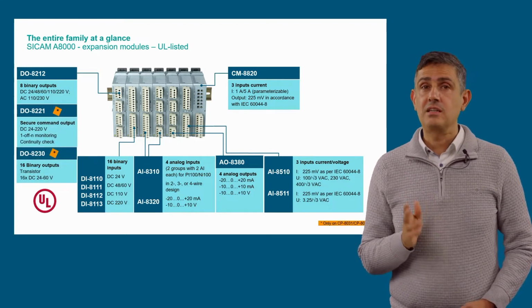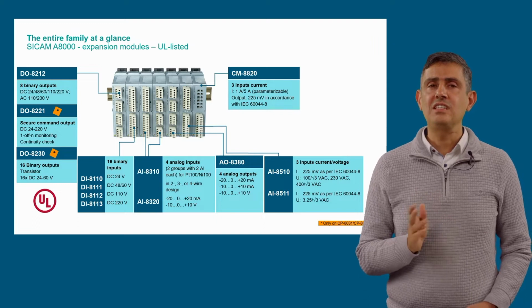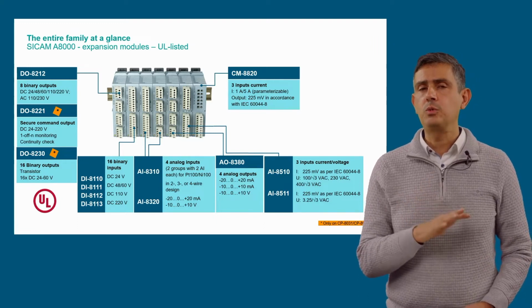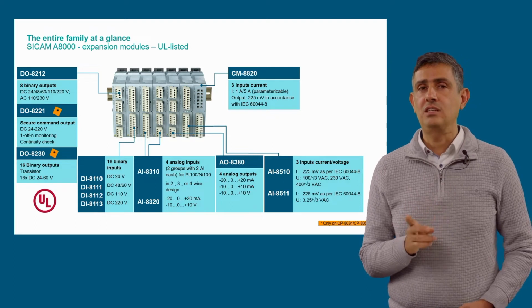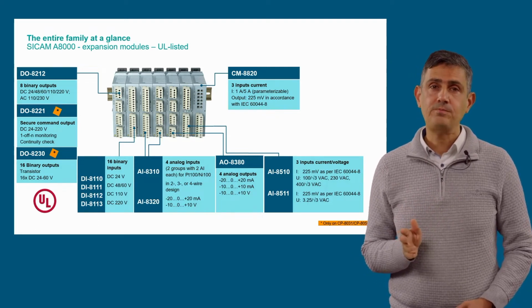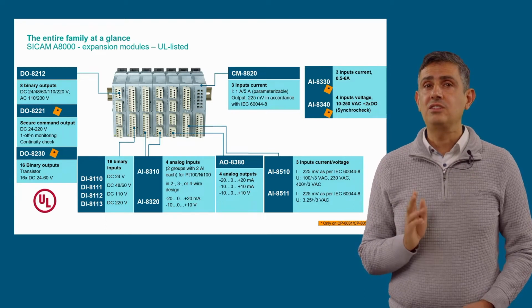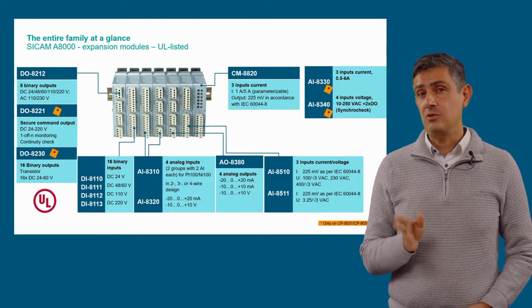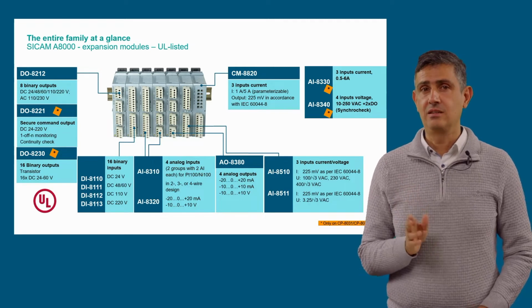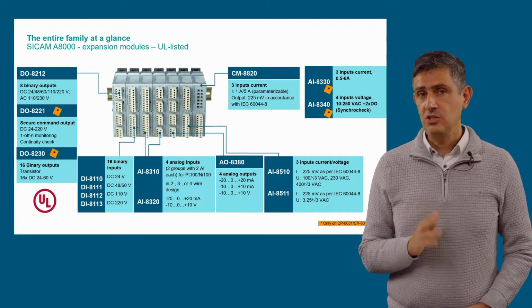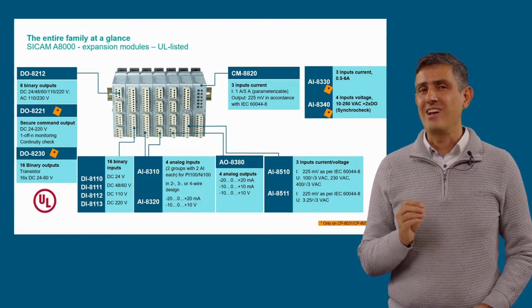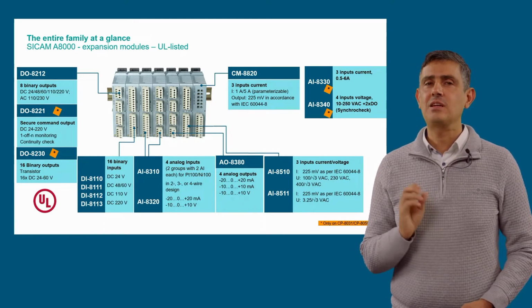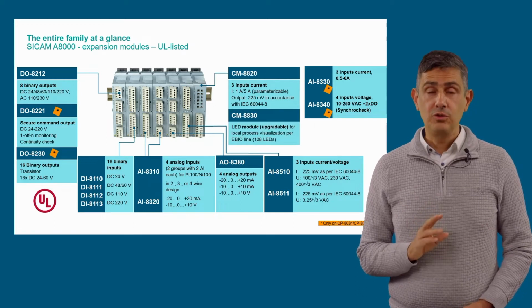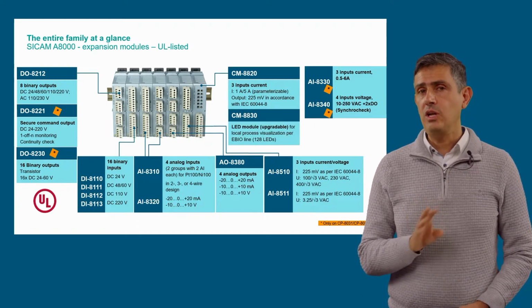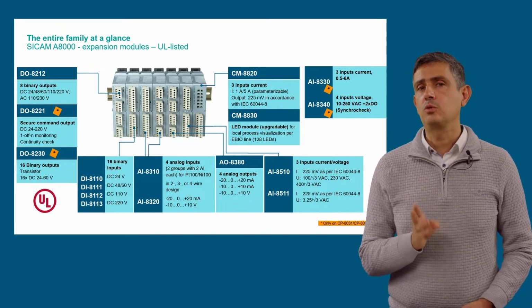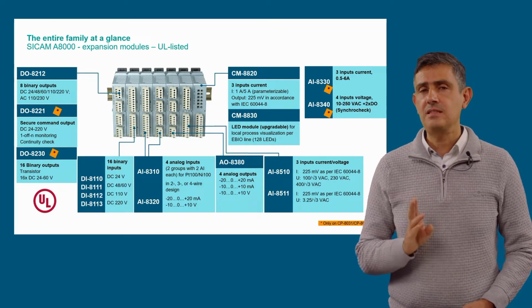For the Linux-based RTUs, we also have additional binary output modules such as the DO8221 with 1 output for secure command and the DO8230 with 16 transistor outputs. Or the additional modules AI8330 and 40 for the acquisition of three-phase measurements, which provide higher sampling rate, and the possibility to perform synchro check for the closing of circuit breakers. So now this RTU can be safely used as a bay controller. Furthermore, there is a LED module to have local monitoring of all inputs and outputs in a group of 8 I/O modules. This is available for all types of SICAM A8000 RTUs.